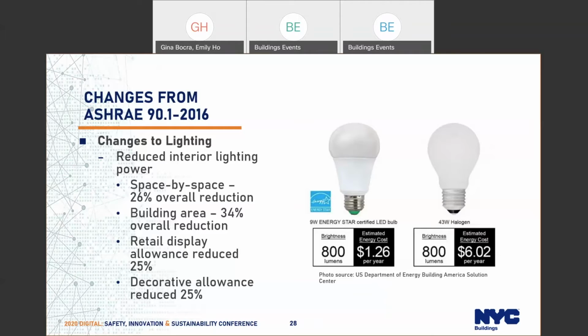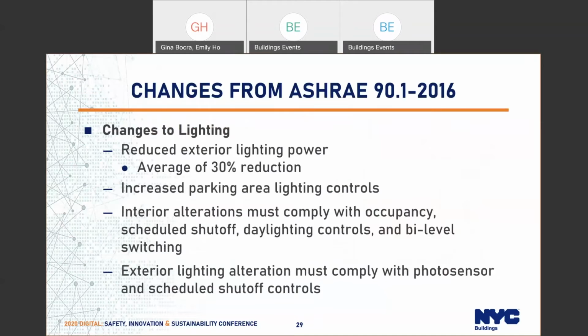We'll talk about what the stretch code did. The stretch code went even further in reducing the lighting power densities. Similar to interior lighting power, exterior lighting power also had a major reduction, by an average of about 30% for the lighting power for outside.